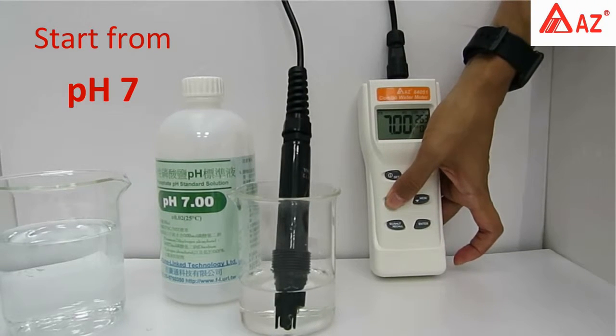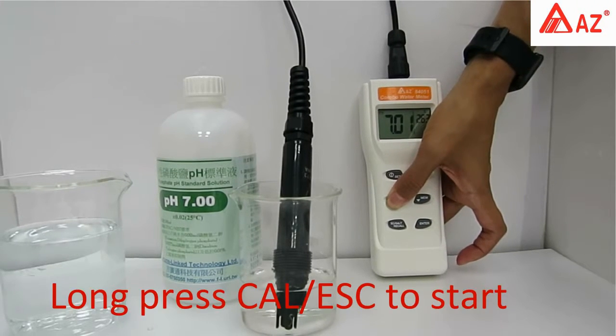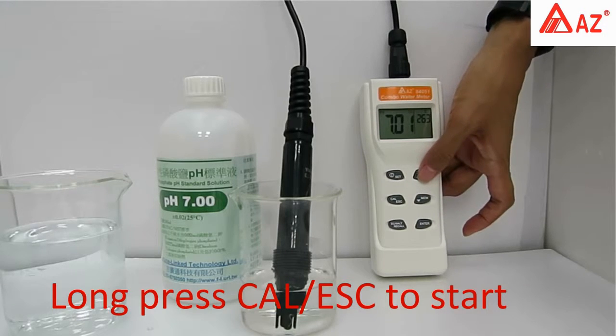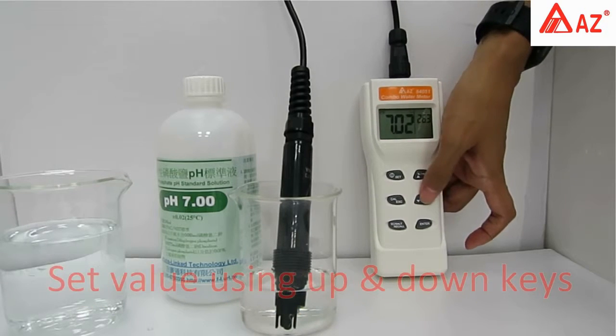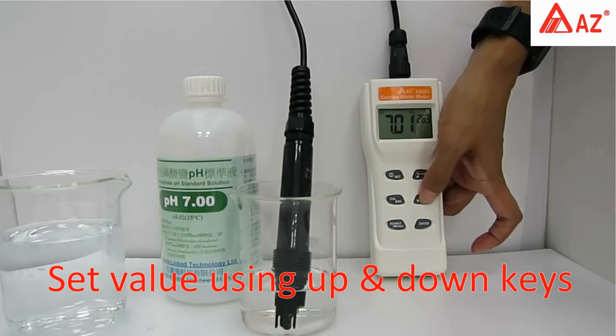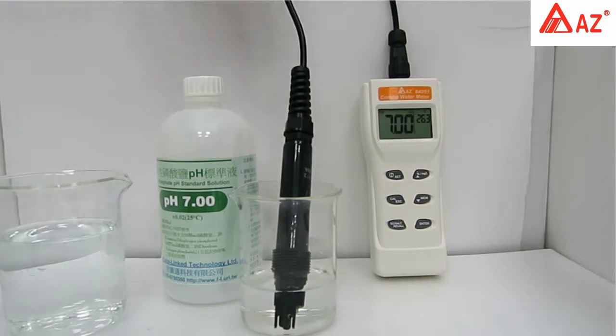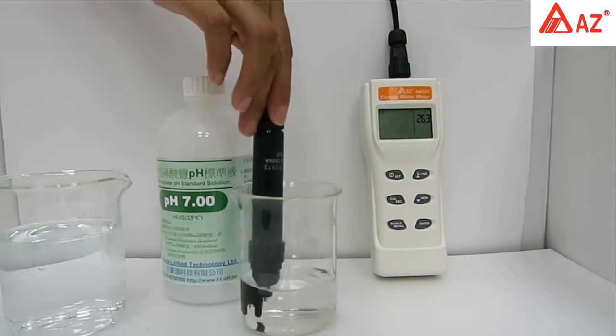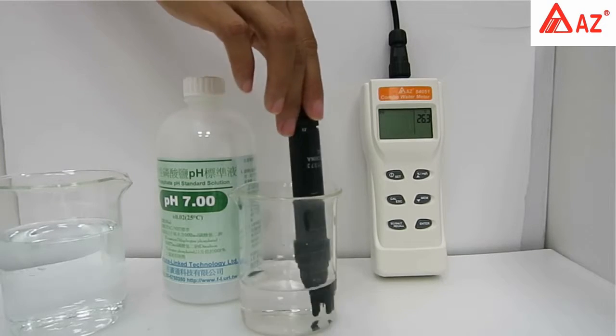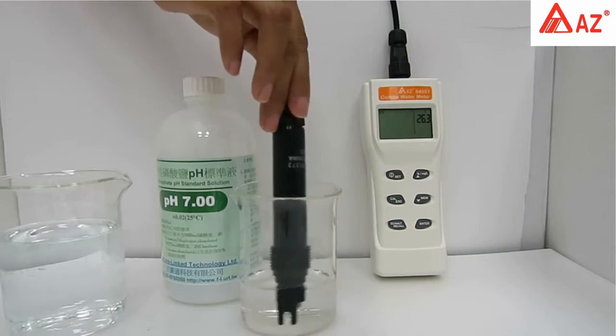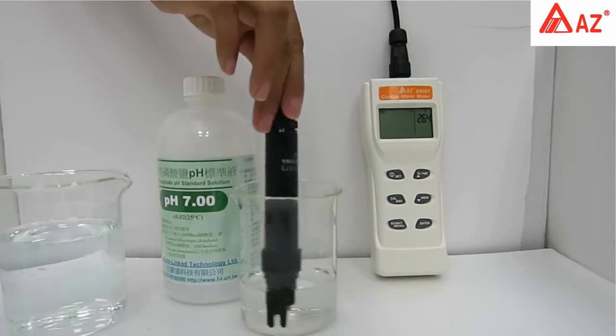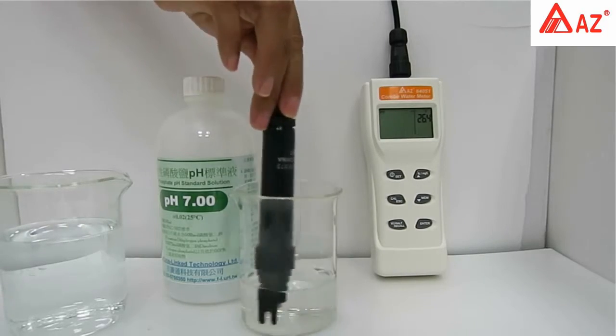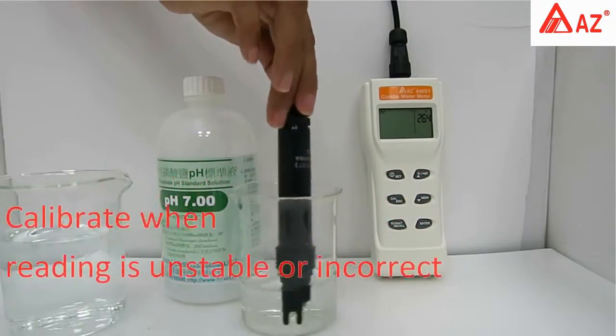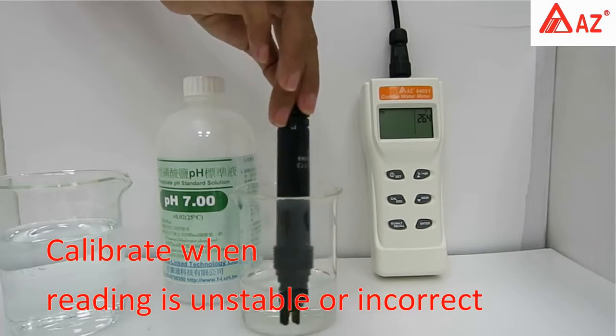pH. Start from pH 7. Long press cal to enter calibration. Set the standard value using the up and down keys. Use a transparent container and make sure the pH electrode is completely immersed in buffer. Stir gently to get a homogeneous condition. Calibrate when the pH reading is unstable or incorrect.